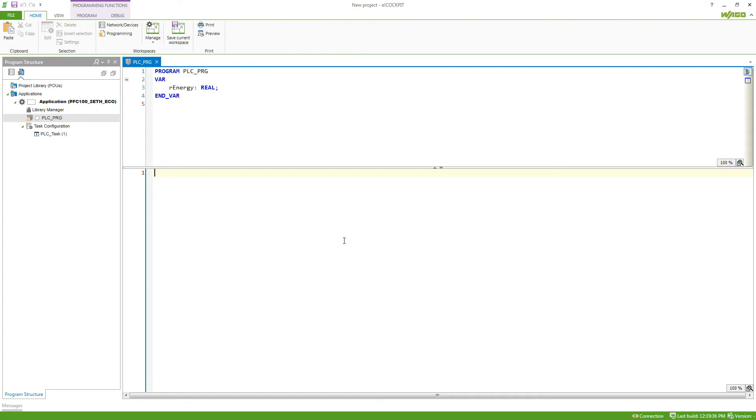In case I want to keep a value, like for this variable here, an energy value, I need to set this variable to a specific memory area. This memory area is called retain.